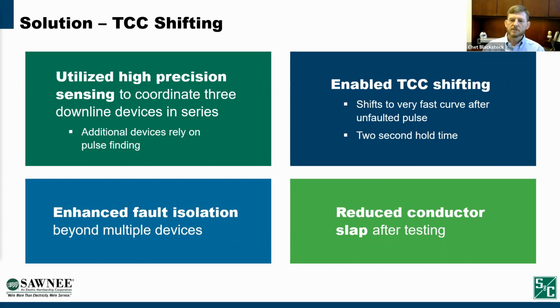So the pulse comes back unfaulted. It shifts to this instantaneous curve. And our setting is for 2 seconds because, as I mentioned earlier, most of our faults recurred within 2 seconds. So during that 2 seconds, it would be on an instantaneous trip. So if that fault re-erupts during that time, it trips instantaneously and maintains coordination. So this helped to enhance our fault isolation toward the end of our system or toward the end of our feeders. And it reduced conductor slap after testing because you allowed less energy on the system.